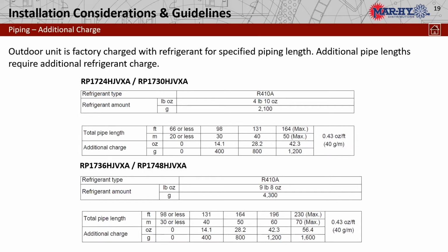Now, on the 3 and 4-ton, that outdoor unit holds 9 pounds, 8 ounces. We are good to 98 feet with no added refrigerant charge. And we can go as far as 230 feet on a total max line. There again, we would add 0.43 ounces per foot after 98 feet. So that's pretty good. Now remember, normally our 3/8 liquid lines would be what? 0.6 ounces per foot. Well, remember with these units, they're a mix of gas and liquid. That's why it's 0.43. That's going to be our multiplier all the time.